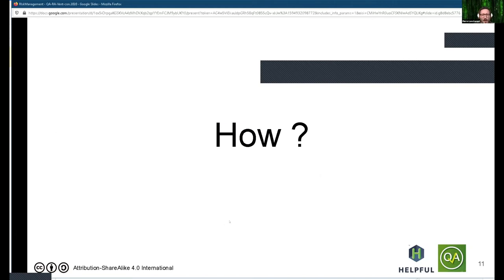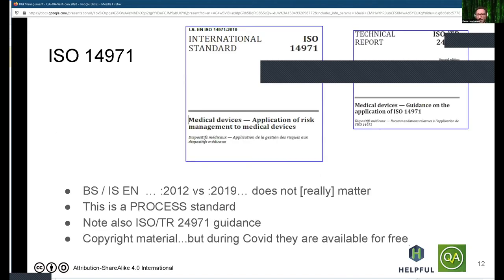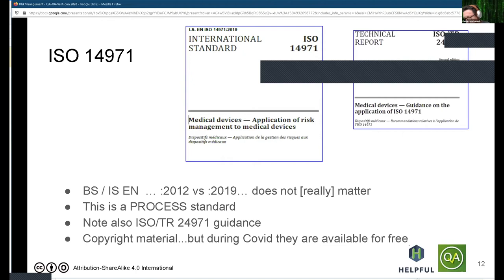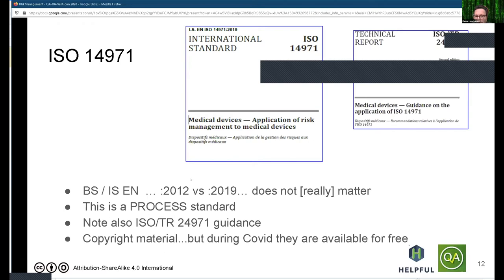Now going into the how. The how of doing risk management in a medical device context is given by ISO standard 14971. There are many versions because this standard is harmonized by the countries that recognize it — sometimes you just see ISO, sometimes you see a British standard, the Irish standard, or EN, with various names on top. There are some minor differences, but I won't go into that today, or the differences between years of issue.